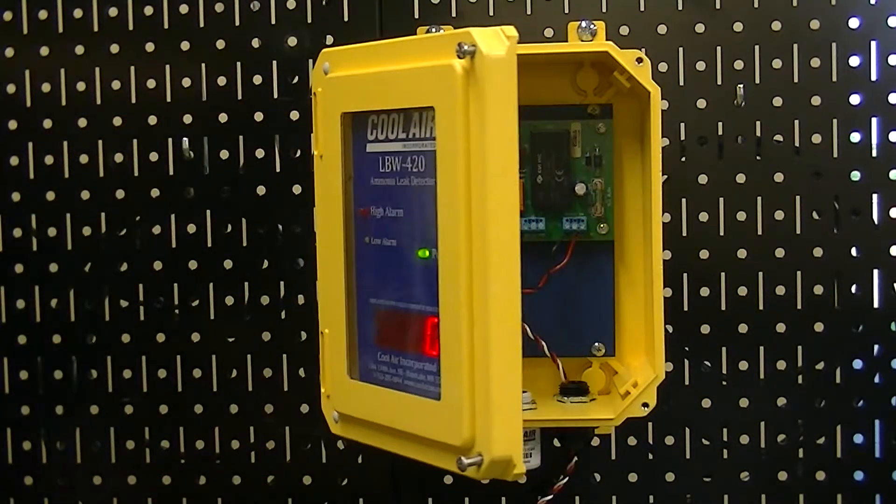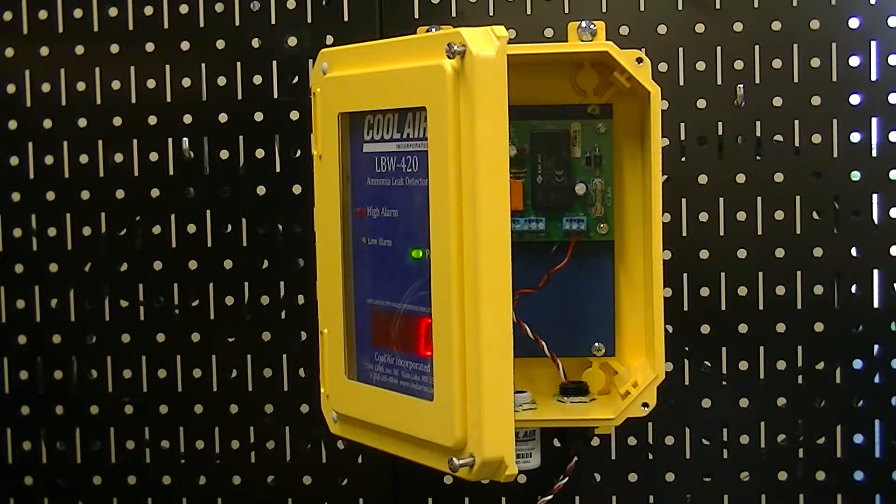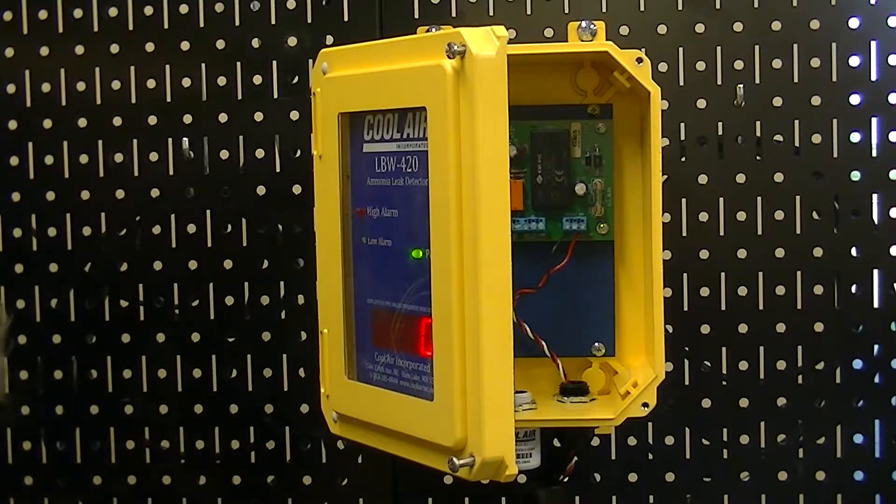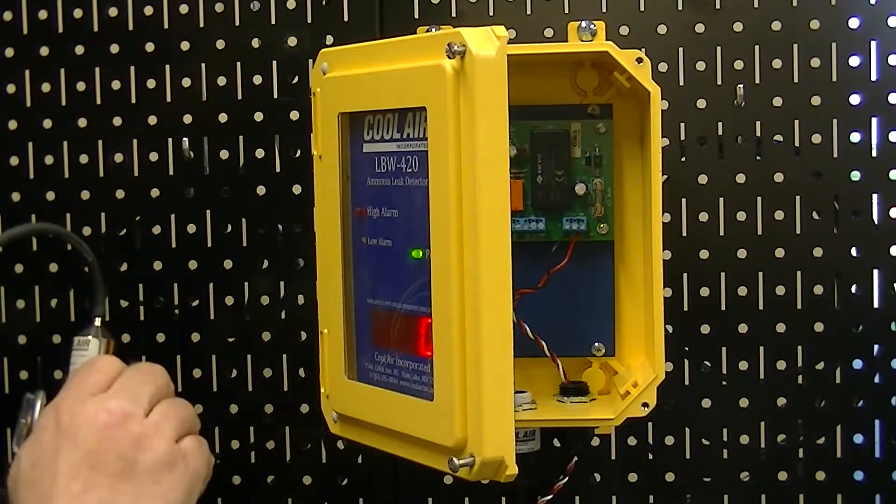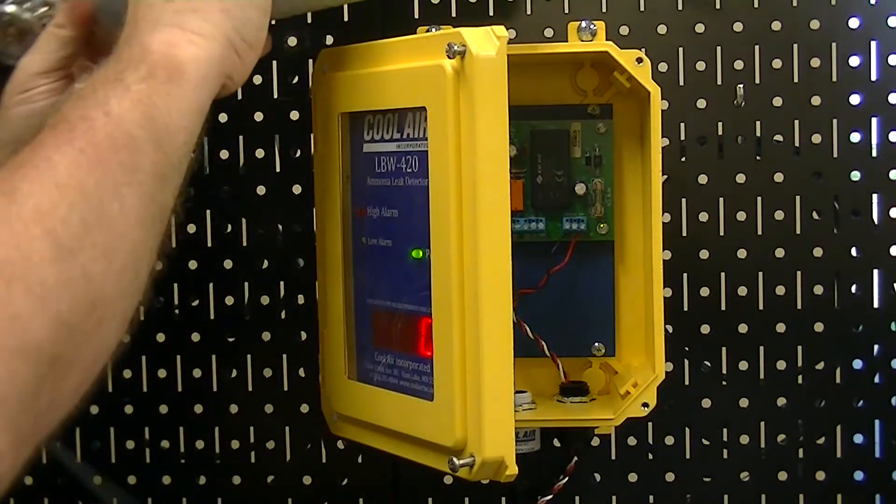We're going to apply our test gas to whatever value you want to calibrate to. I'm calibrating to 100 ppm. I'm going to connect the connector to the sensor, turn the test gas on at a flow rate of 0.3 liters per minute.